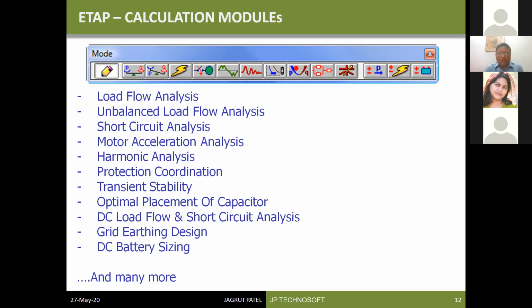To know the behavior of that, DC load flow and short circuit analysis is performed. When we are working with large substations like 66 kV, 132 kV, 220 kV, there will be a specific earthing requirement, which is called the grid earthing network. Below ground, there will be an earthing network generally provided. To size that earthing network, we need to perform a grid earthing design calculation. This is also possible with ETAP. Then DC battery sizing. This is applicable to the DC load, or when we are working with UPS batteries; this DC battery sizing calculation is generally used. Apart from that, there are small tools available with ETAP, which are part of their equipment modeling menus. This will come for one or two menus. We will show you how to perform these calculations.